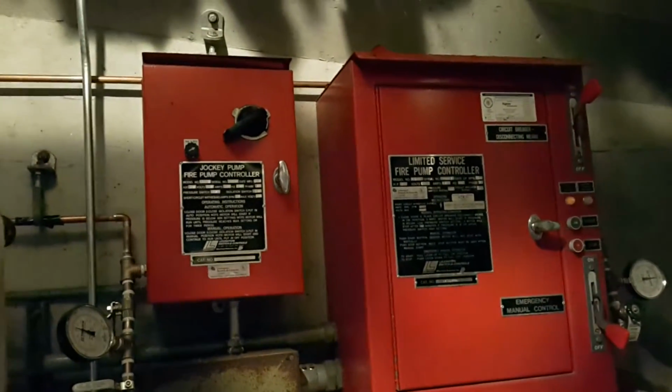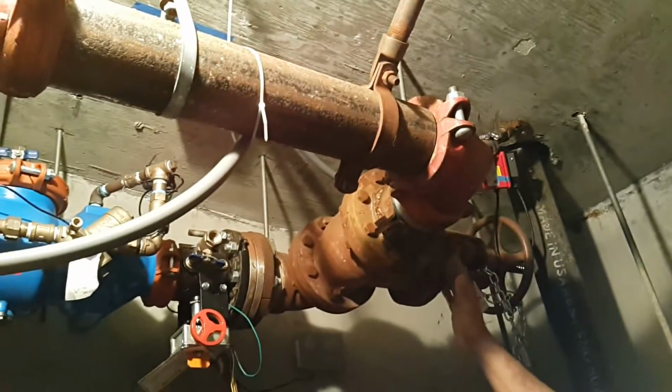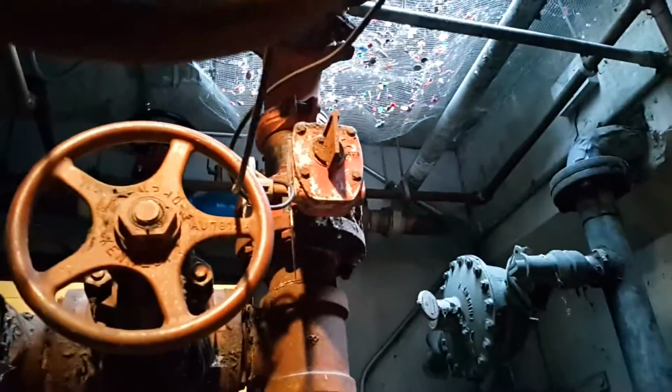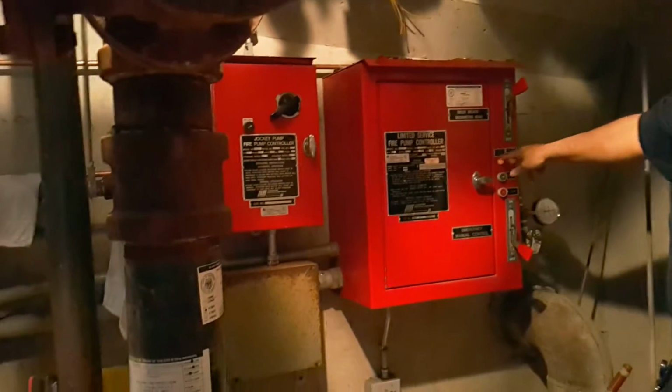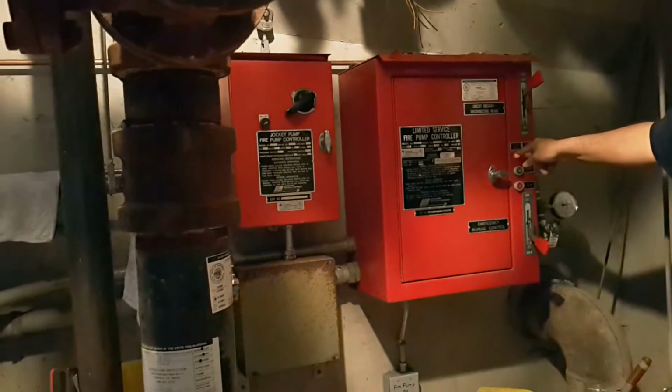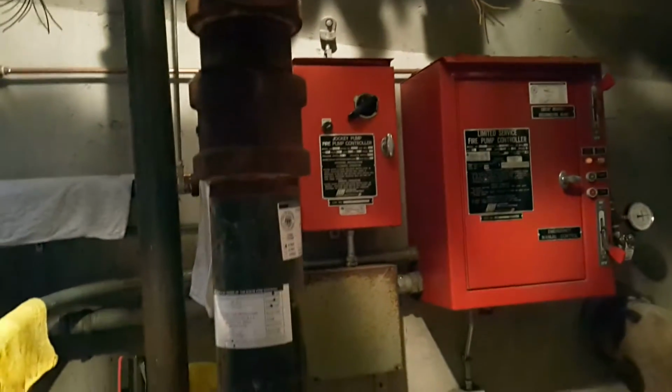When you check your valve alignment, making sure the valves are all aligned correctly, you're looking for is making sure your city is open. This is your main valve. Your bypass is open. See how they check the alignment. Your test loop is closed. These are closed. And your fire pump discharge is open. All right, that's on your main fire pump. And you also have to make sure that you have power available. That's very important, because if that light is not on, two things: either the light bulb is bad, or you have no power to the fire pump.